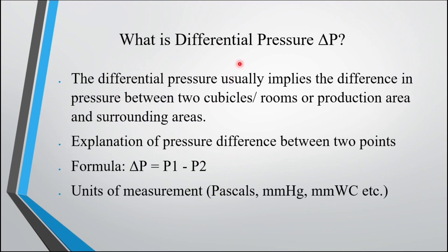What is differential pressure or delta P? Differential pressure implies the difference in pressure between two cubicles, two adjacent rooms, or between the production area and the surrounding area. The formula is: ΔP = P1 − P2. Units of measurement are Pascals, mm of mercury, or mm of water gauge.